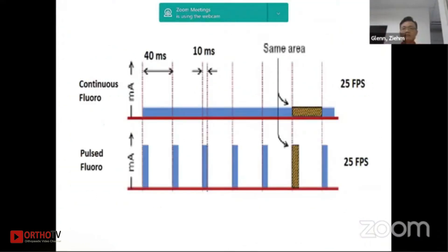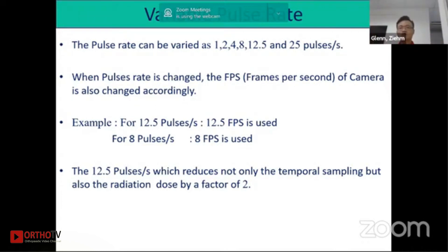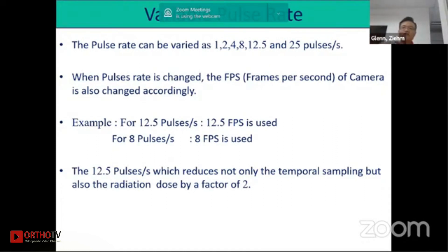This diagram shows the difference between continuous and pulse fluoroscopy. With pulse fluoroscopy there are different power levels, and we have a variable pulse rate. For extremity procedures where there's no movement you can have one pulse per second, saving dose. You have a variable range of 1, 2, 4, 8, up to 25 pulses per second. When the pulse rate is changed, the frame per second of the camera is also changed — for 12.5 pulses you get 12.5 frames per second.